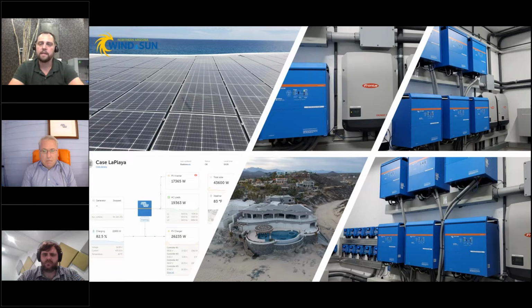The system has about 85 kilowatts of solar power. 50 kilowatts of that is DC coupled, 35 kilowatts is AC coupled. The system is a three-phase 120/208 volt configuration with a 60 kilowatt inverter system, and it includes about 200 kilowatt hours of lithium battery storage.